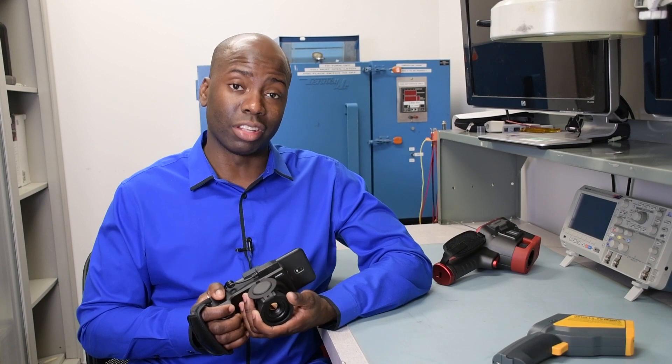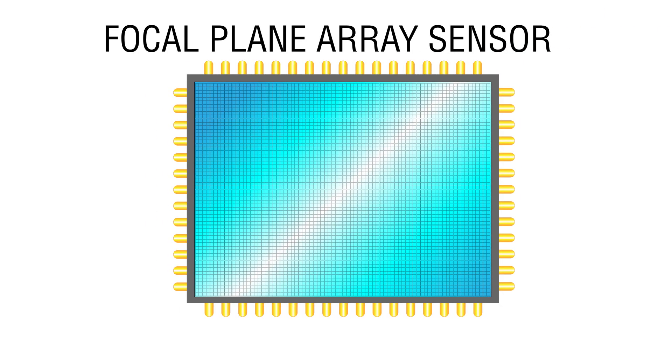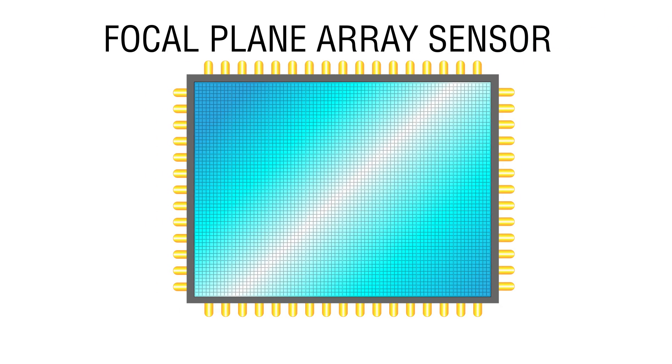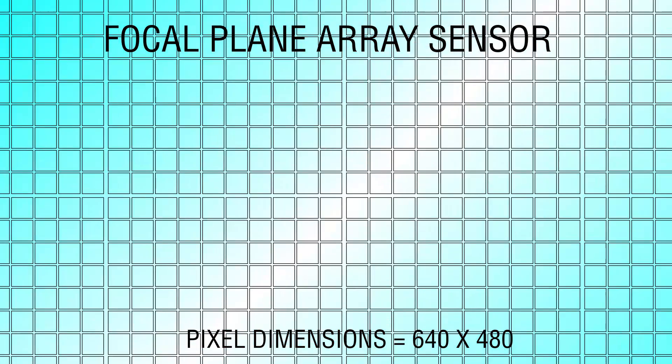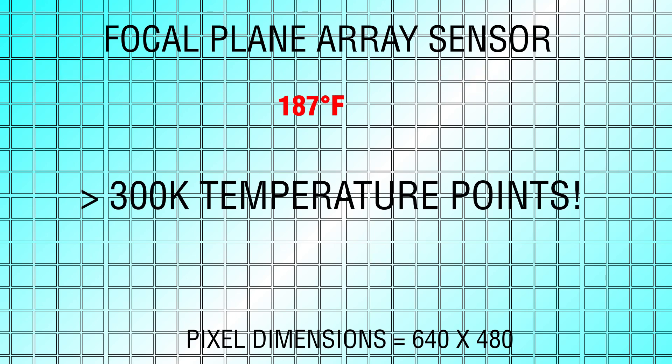Meanwhile, a thermal imaging camera like this one uses a focal plane array sensor. This thermal imaging sensor has pixel dimensions of 640 by 480, and with each pixel acting as a sensing element, that gives you over 300,000 individual temperature points on each thermal image or video.